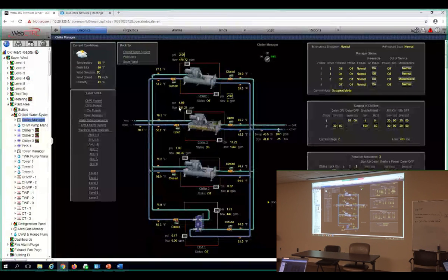Usually I can run the water through one tower. That won't take long before that other one has to kick on because the water temperatures will get it. So I don't have a long delay. I'm only proving the second one for about a minute right now. They start pretty reliably, but I may decide that it's 5 minutes or something, then shut that other chiller down. We can adjust that. First thing I want to get fixed is these pressures, they're a little slow, so that I'm going to start rotating. As soon as those are fixed, I'll start rotating the chiller.